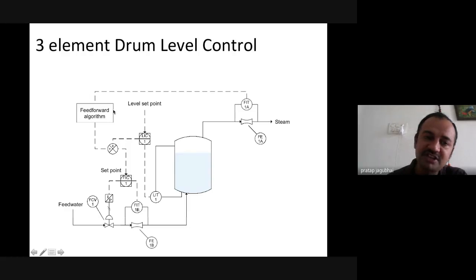In the feed forward action with the multiplication, some factor will be taken here, and the level input is taken from the tank, and the feed water flow is also taken in advance, such that the corrective action for the control valve or the VFD of the feed water flow pump will be regulated in a more useful manner, and less effect of the shrinking and swelling will be present.